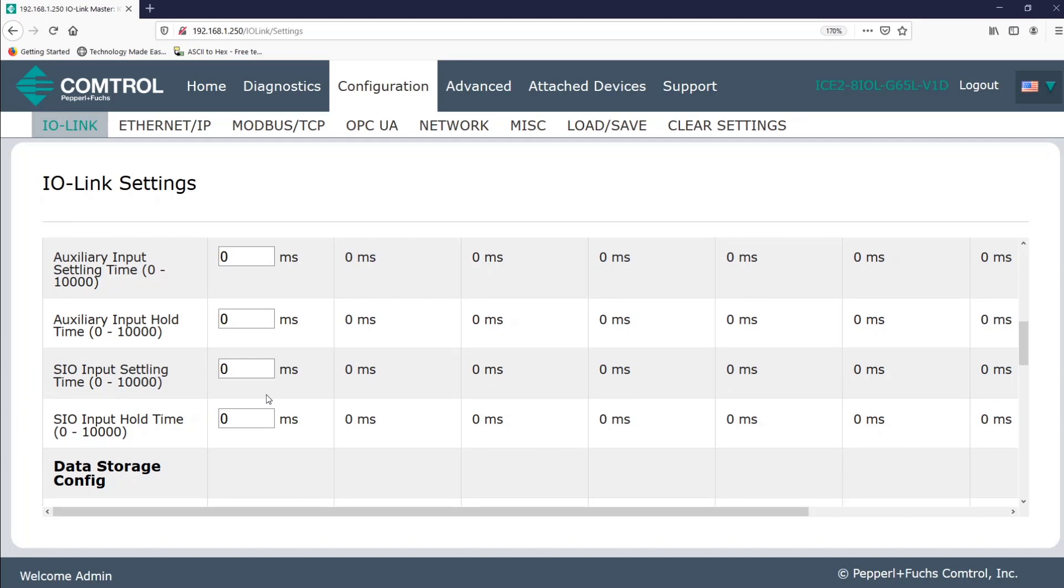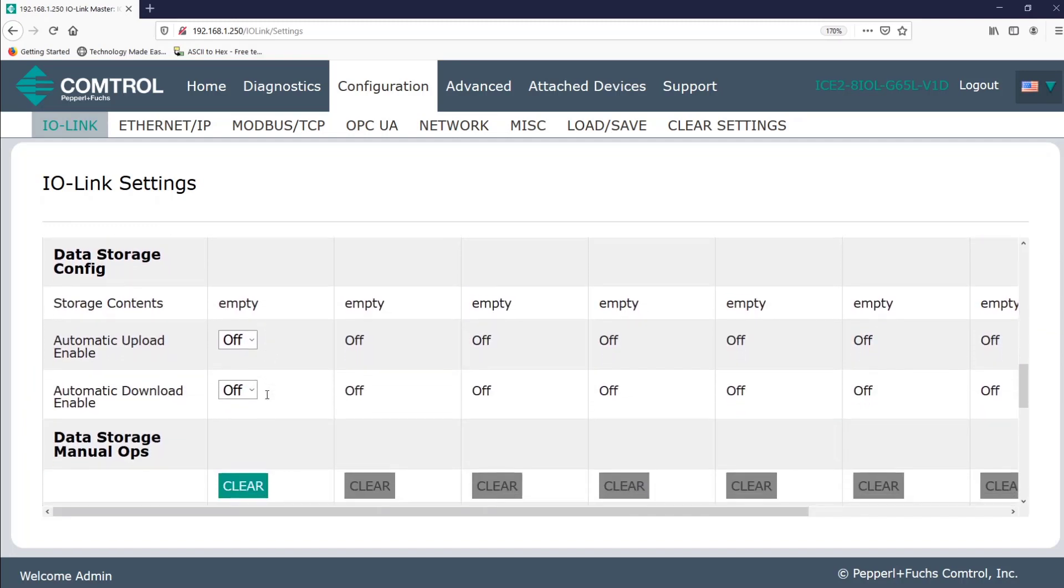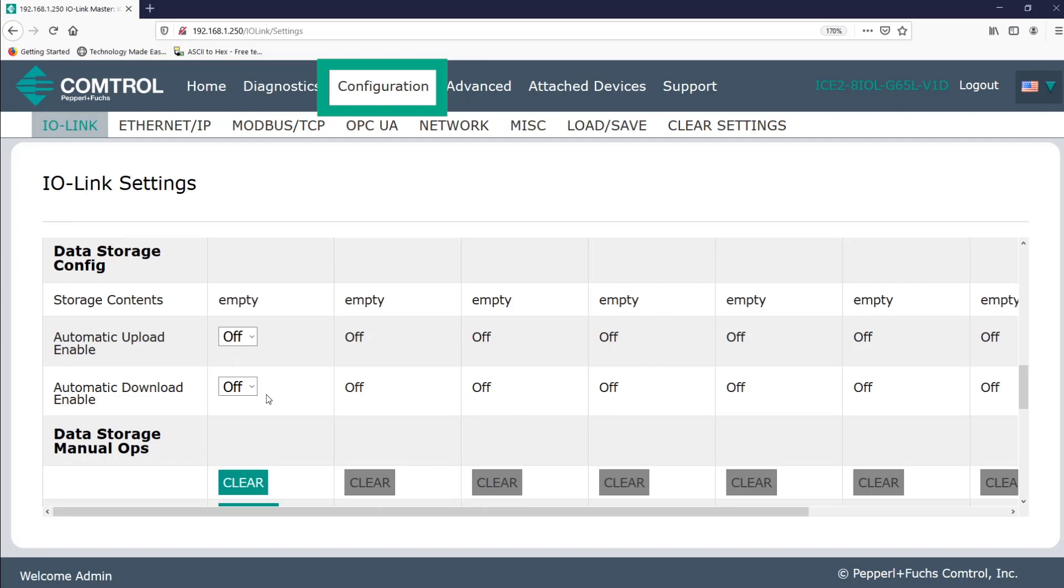So next is data storage configuration. First, realize that data storage relates to the device settings, which are actually stored on the device itself. In this case, my RFID head. The configurations on this screen are for the port, which is on the IO link master. If I remove my RFID head from port one and replace it with an ultrasonic sensor, these settings won't change because port one didn't change. I just connected something different to it. Data storage simply indicates whether a port should upload or download a device's settings and whether or not to do this automatically.